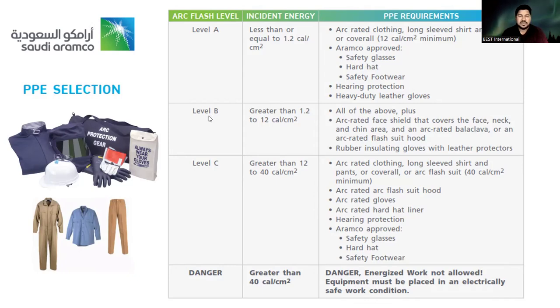Now, if it is level B, greater than 1.2 to 12 calories per square centimeter, then all of the above, whatever level A required, plus an arc rated face shield that covers the face, neck, and chin area, and arc rated balaclava or an arc rated flash suit hood, rubber insulated gloves with leather protectors. Since level B is more dangerous, not only the PPE mentioned in level A, there are some additional items that should also be added if you are sending your guys to work under level B conditions.